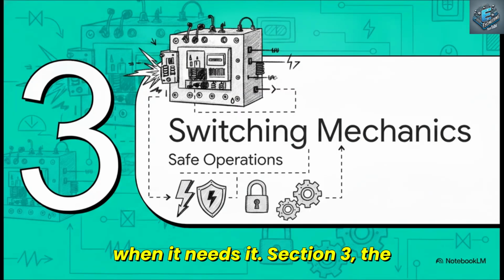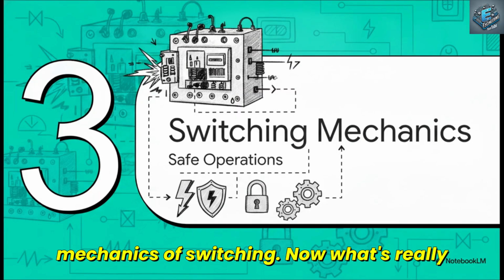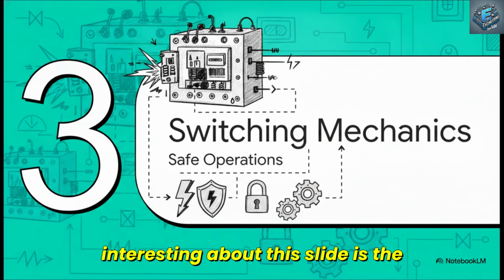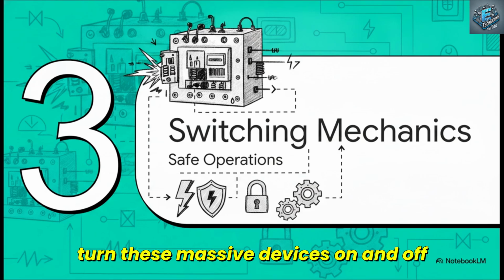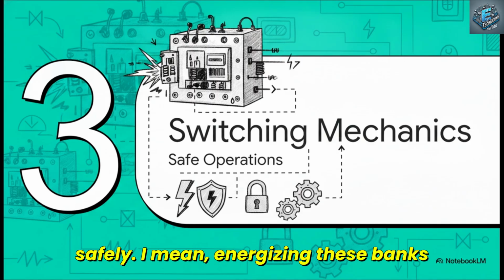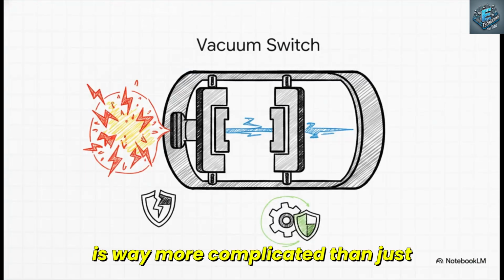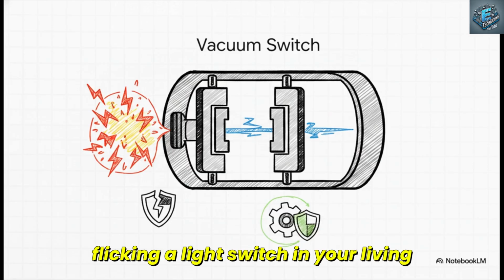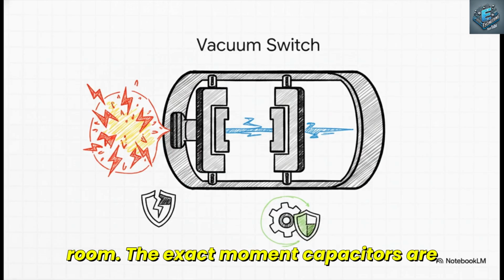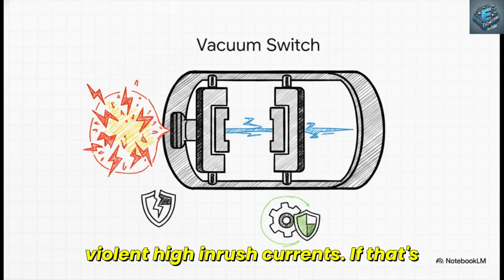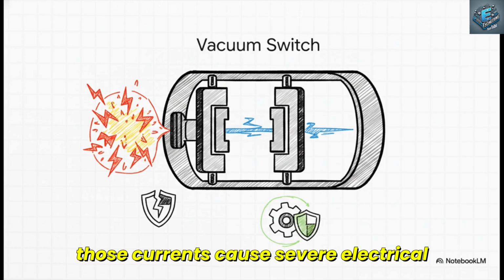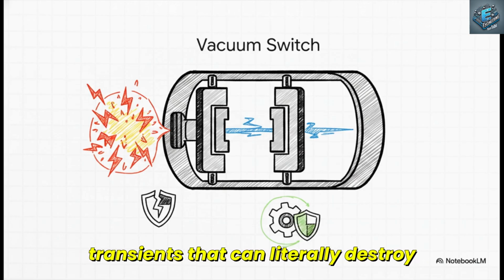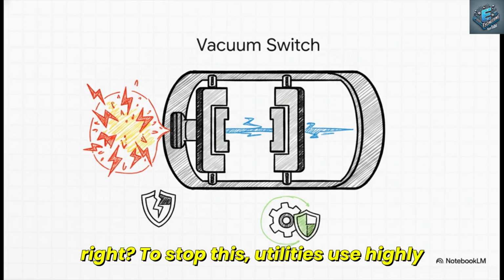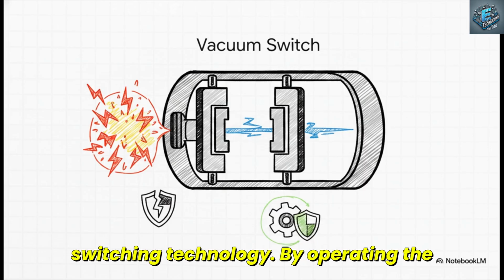Section 3, the mechanics of switching. Now, what's really interesting about this slide is the intense engineering it actually takes to turn these massive devices on and off safely. Energizing these banks is way more complicated than just flicking a light switch in your living room. The exact moment capacitors are energized, they can generate incredibly violent, high inrush currents. If that's not controlled absolutely perfectly, those currents cause severe electrical transients that can literally destroy your equipment. No way you want that, right? To stop this, utilities use highly specialized gear, specifically vacuum switching technology.